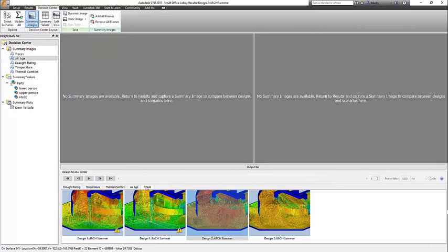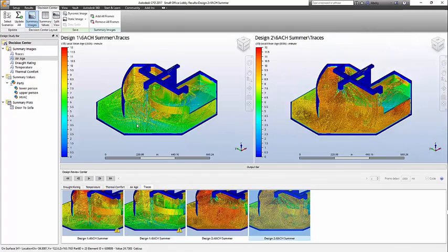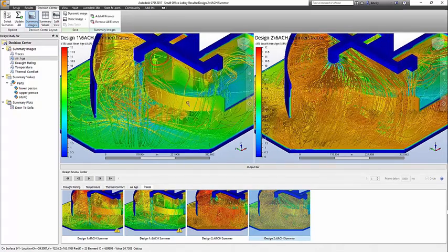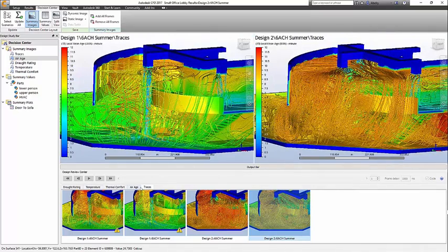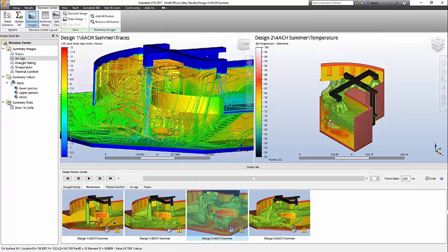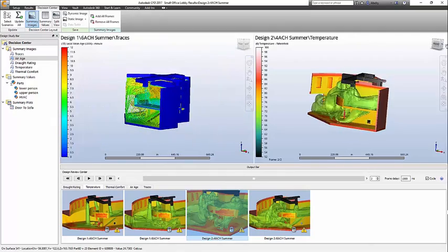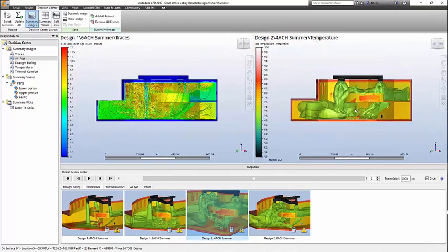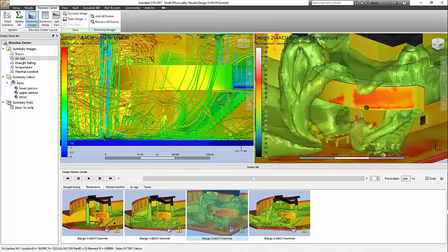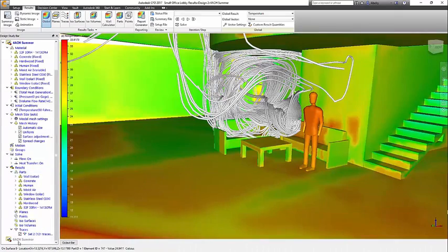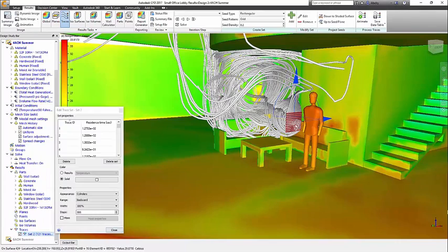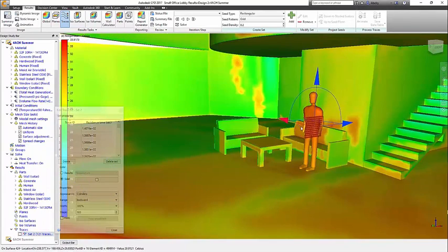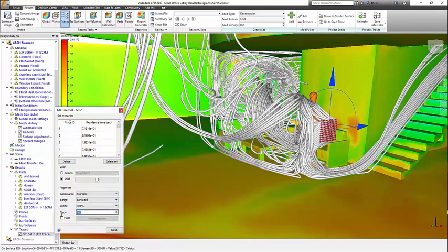Let's now be more selective on what we're comparing. The viewports and thumbnail images allow for quick drag and drop to populate the storyboard you're interested in showing. Flow traces can get busy quick, but they do display the flow along the walls very well. The trace density represents mixing and can show areas of trapped flow that isn't getting recirculated. I'm still interested in understanding the flow pattern in the seating area a bit more. A great way to investigate this is to seed traces and only show where they came from. This clearly shows a coil-like airflow underneath the mezzanine.